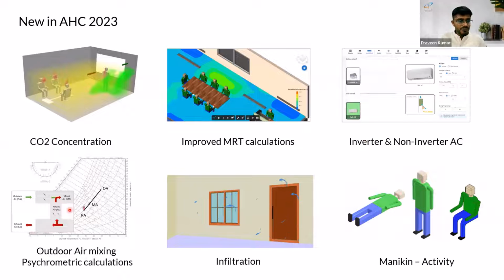Another highly requested feature was adding outdoor air mixing in the app, for CAV, VAV, or even cassette systems which provide outdoor fresh air addition, so these can be modeled accurately. We've now included psychrometric calculations, which calculate supply air conditions, temperature and humidity, more accurately based on the return air and the ratio of mixing with the outdoor air.